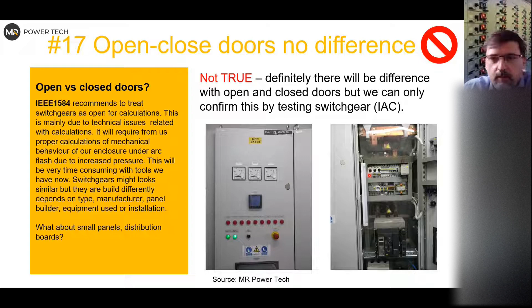It's an interesting point which I'd like to highlight. So we have internal classified panels and we think we're all safe. That's not true, because you need to be aware how this internal classification works. We can have it for low voltage, which is rather rare to see, but very common to see is internal classification for medium voltage systems. Just the fact that something is internally classified doesn't remove the danger and doesn't remove all the responsibility behind it.